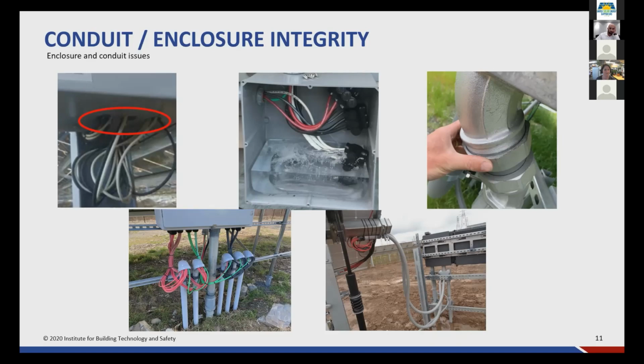Conduit and enclosure integrity issues, like freezing water inside enclosures. On some of these larger systems there can be up to 1500 volts DC power going through there, so you don't want water anywhere near that. And second, freezing can break the enclosures and cause even more problems.